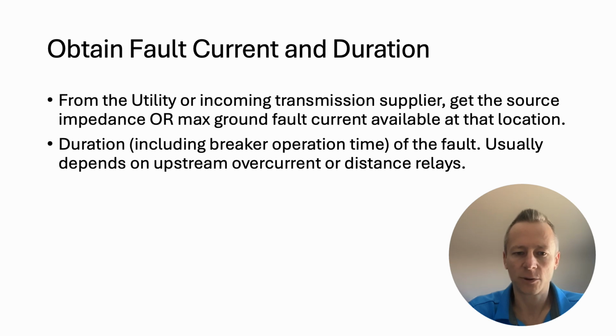All right, leaving the soil resistivity, the next thing that you're going to need is the fault current duration and the amount of fault current. Typically get that from the utility or whoever owns and supplies the incoming transmission to your substation or your site. So a lot of times if you have source impedance at the transmission interconnection, that's fine. You can use that to calculate the maximum ground fault current. But then you'll still need from the utility the trip time associated with that max ground fault current.